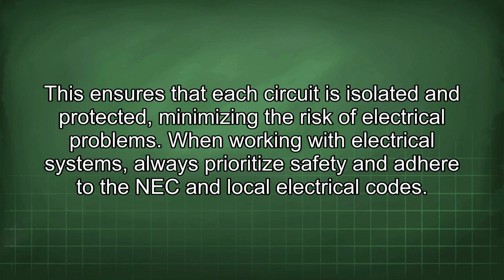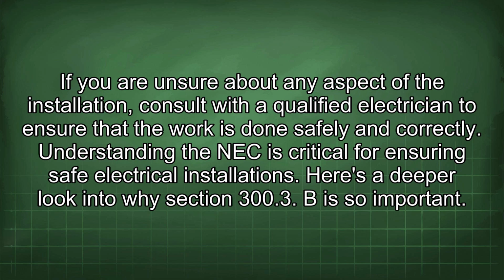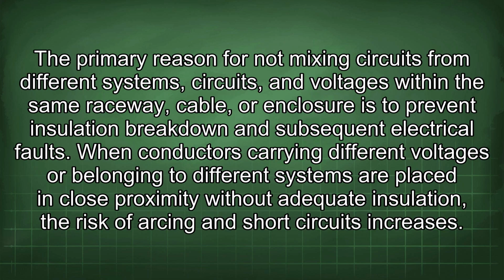When working with electrical systems, always prioritize safety and adhere to the NEC and local electrical codes. If you're unsure about any aspect of the installation, consult with a qualified electrician to ensure that the work is done safely and correctly. Understanding the NEC is critical for ensuring safe electrical installations. Here's a deeper look into why Section 300.3 B is so important. The primary reason for not mixing circuits from different systems, circuits, and voltages within the same raceway, cable, or enclosure is to prevent insulation breakdown and subsequent electrical faults.